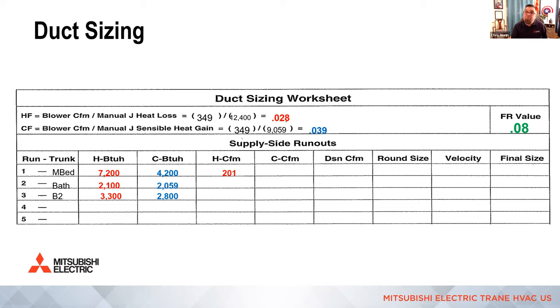Of course, we're going to figure out if we're going to design around heating first. We're going to do cooling BTUs for the master bedroom, the 4,200 times 0.039 for the cooling factor gives me 164 CFM. So in this example, we have a higher heat loss for the master bedroom in volume of air that's needed compared to the sensible heat gain. So we don't always design around the cooling needs, right? So our design CFM is going to be the larger of the two, the 201.